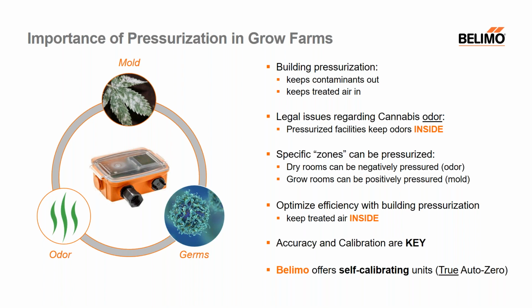Think about shaking up a bottle of soda and opening the cap right away. The soda is forced out because of the built-up pressure within the bottle itself. On the other side of things, a building or space that's negatively pressured will keep the air within itself, and when a window or door is open, outside air will actually enter the negatively pressured space. Have you ever tried to open the door to a building in the wintertime and the door feels near impossible to open? The reasoning for this is the fact that the building you're trying to enter is negatively pressured, and you have to physically overcome this pressure difference, or differential pressure, to open the door.